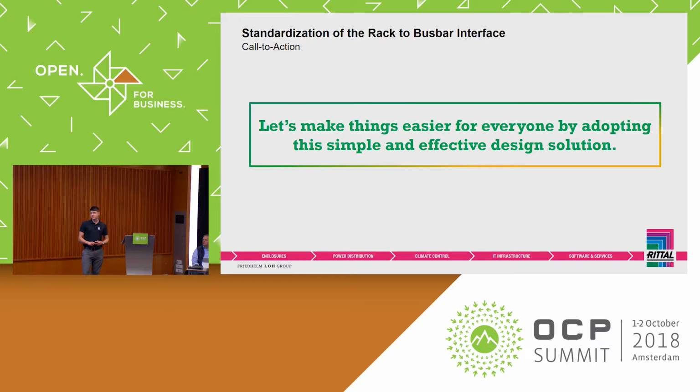We've had some problems with customers, that's the idea, where they've been putting power equipment and things in there. So was the power equipment you were using OU equipment? Yeah. And did you order the bus bars specifically for the position you needed, or did you have to modify for your needs at your site? We had to do some drilling to fix the bus bar to the rack.